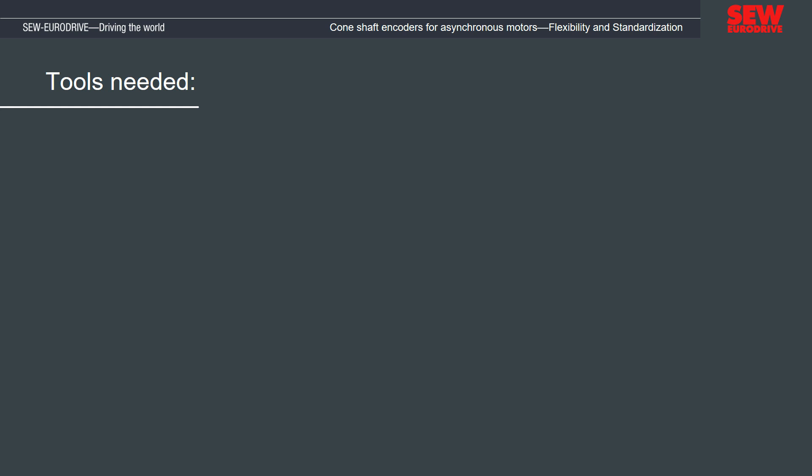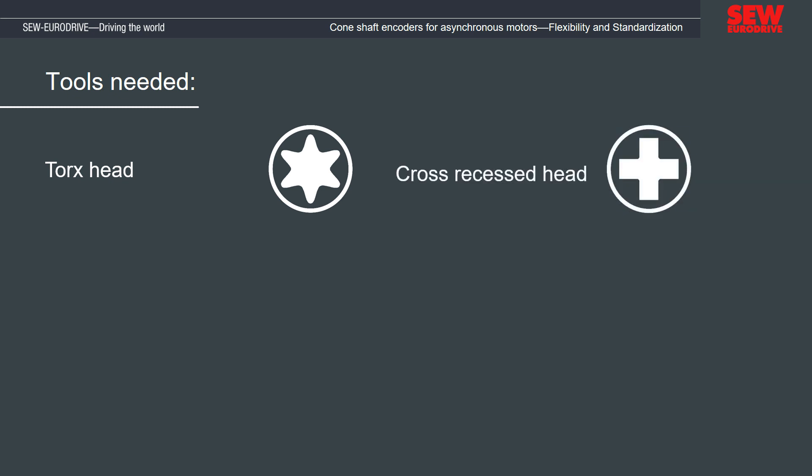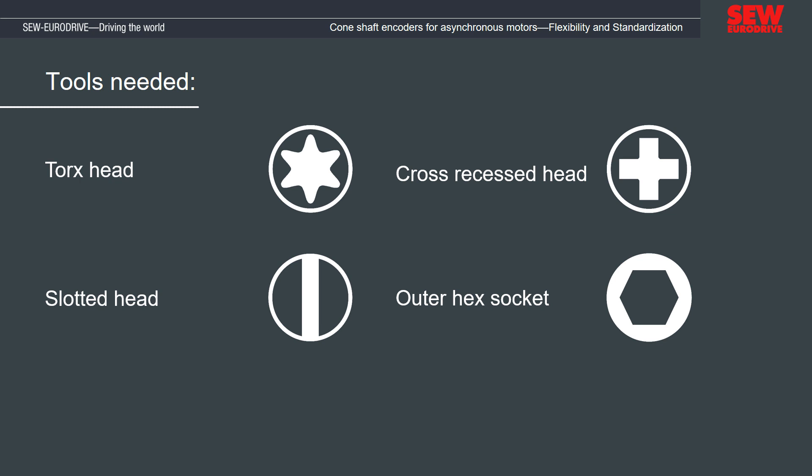In the following, we would like to explain what must be considered when disassembling and assembling the cone shaft encoders. To work on the SEW EuroDrive cone shaft encoder, we will need the following tools: Torx screwdrivers sizes T20 and T25, screwdrivers for cross-recessed head screws size 2, for large slotted screws, and an outer hexagon socket size 8. For the assembly, a torque wrench with the appropriate bits is required. The corresponding tightening torques are listed in the operating instructions.